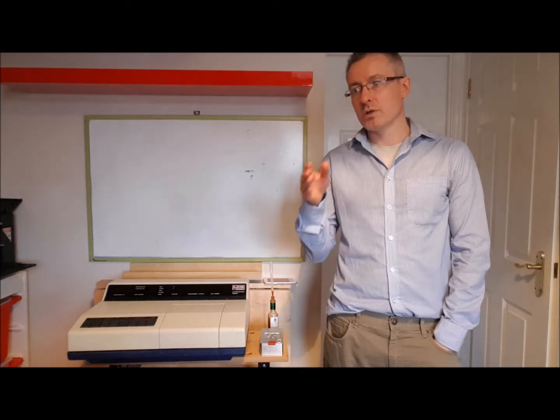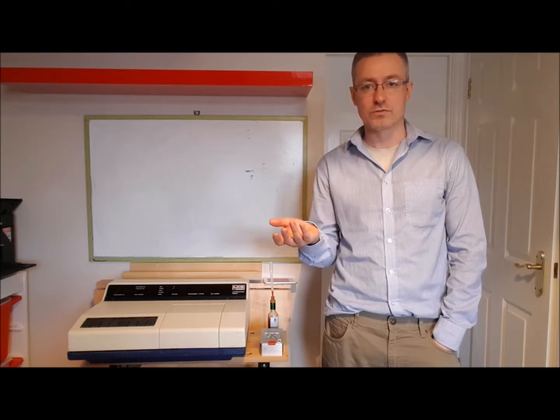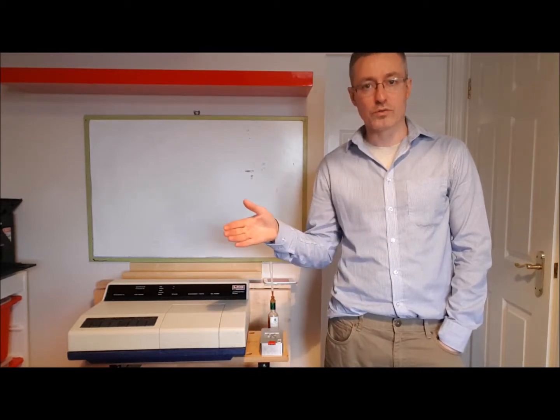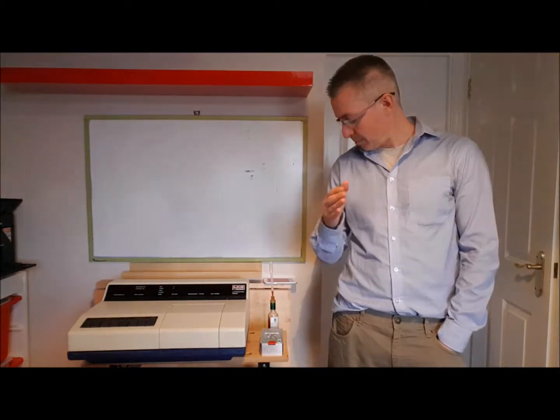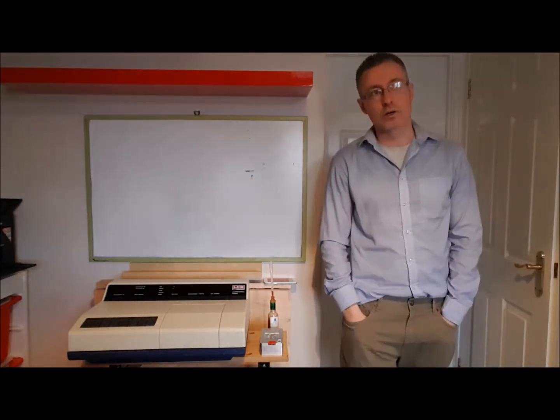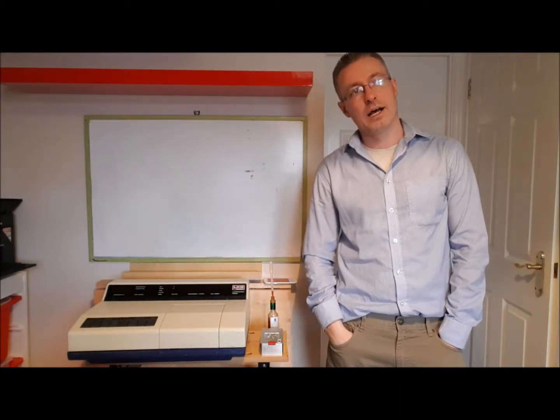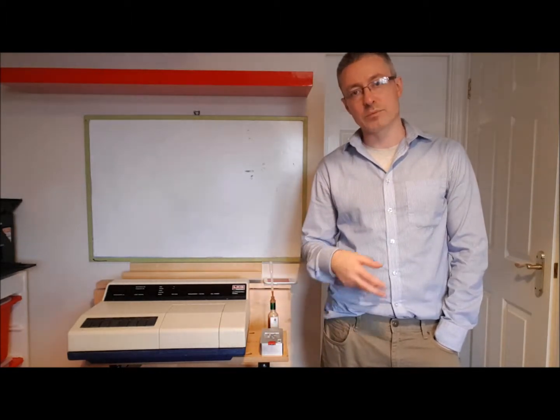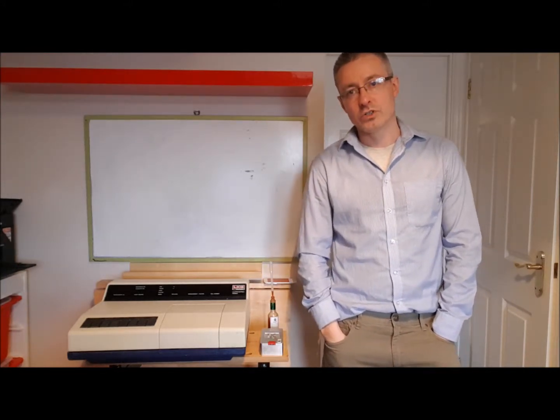People ask us to tell them the difference between the HPLC method and the Chili Pot Scoville meter for measuring the hotness of chilli. The chromatography part involves a column packed full of material that allows for separation. Those columns retail for at least around $500 US dollars, and I'm being quite lenient on the cost there. The column also has to be periodically replaced.